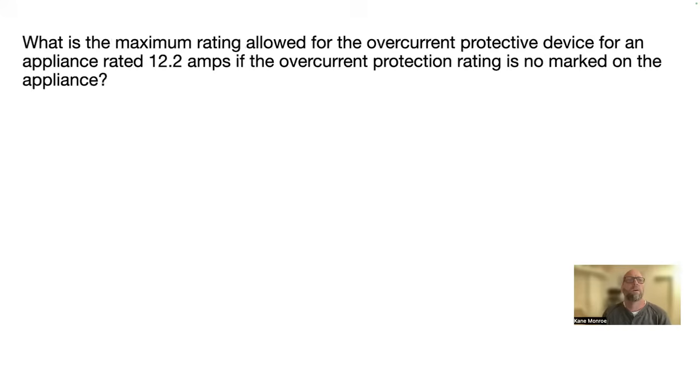Next one. What is the maximum rating allowed for overcurrent protective device for an appliance rated 12.2 amps if the overcurrent protection rating is not marked on the appliance? 20 amps. Maximum allowed overcurrent protection is 20 amps. That's in 422.11 E2. Make sure you guys are highlighting those.